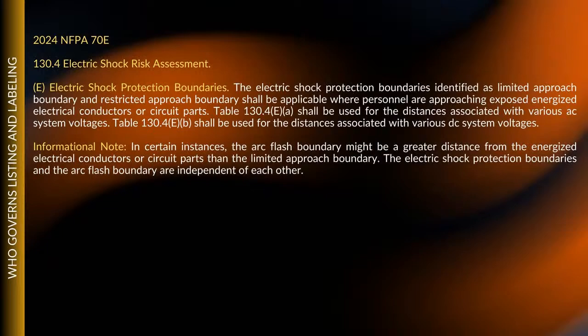This is the last part. You get into the electric shock protection boundaries. Well, guess what? It depends on what the voltage is. Now, all of a sudden, you got to look at this. If I'm in that transformer and it's a higher voltage transformer, all of a sudden that 3 foot is nothing. I may need 4 foot. Because you would be working on this when you're inside the limited approach boundary.